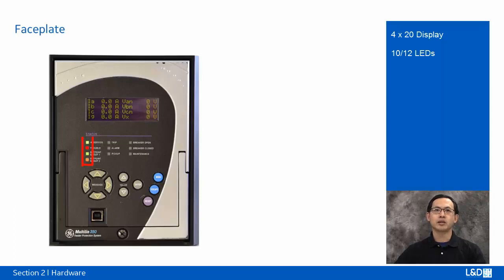LEDs can be red, green, or orange. The keypad allows users to navigate through the hierarchical relay menu, change the set points, and reset the trip and alarm status without using a computer. In addition to the front panel operation, the USB port is intended to connect to a PC loaded with EnerVista SR3 software. A setting file can be created offline and then downloaded into the relay through this port with the program.